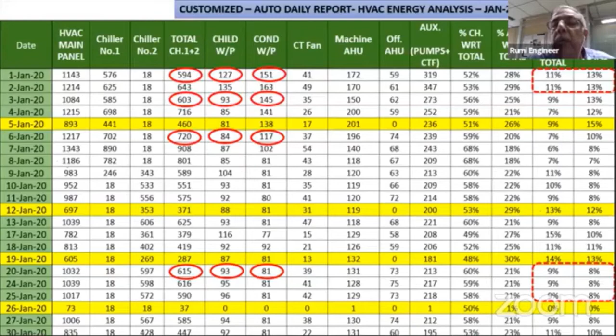My chiller is being loaded and unloaded because it's January, a cold month, at 5,500. My chill water pump is consistently at 3.22 and 4.7. But on the 1st of January, for 594, my chill water consumption and condenser water pump were still high. You know what happened?